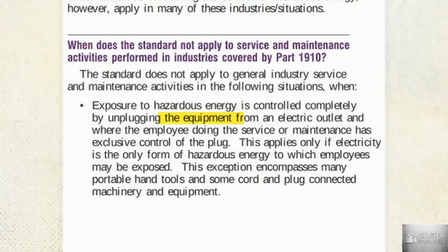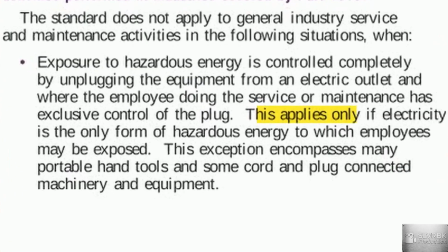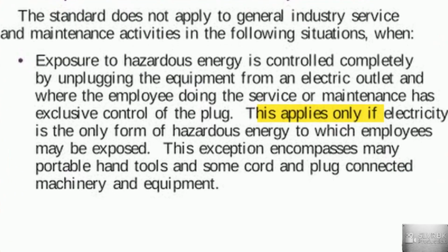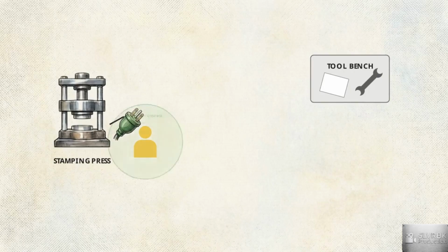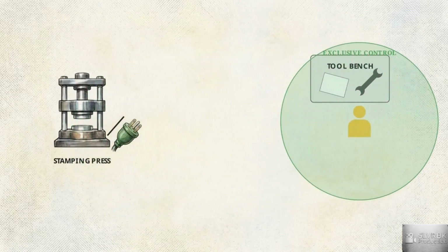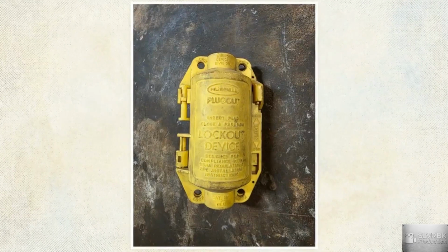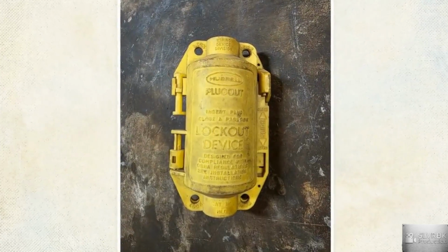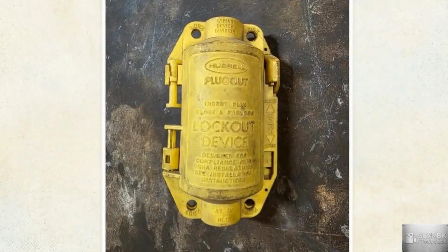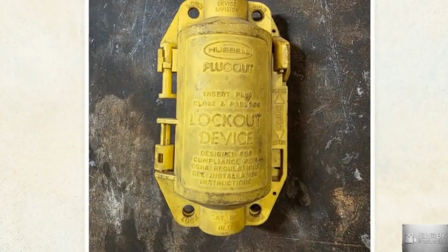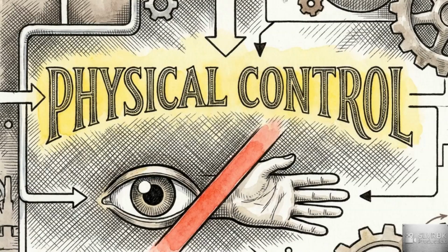As we see in this OSHA documentation, the cord and plug exemption allows bypassing full lockout if electricity is the only hazard, delivered via standard plug. However, the employee doing the service must maintain exclusive control of the unplugged cord. Walking away from the unplugged machine immediately breaks that exclusive control. Stepping across the room to grab a wrench means you can no longer guarantee someone else won't plug the equipment back in. When control is broken, a physical barrier is required. Here, we see a yellow plug-out device securing the cord end so it cannot be inserted. Distance destroys control. If you cannot physically keep your hands or eyes on the plug, a physical lock is mandatory to prevent accidental re-energization.